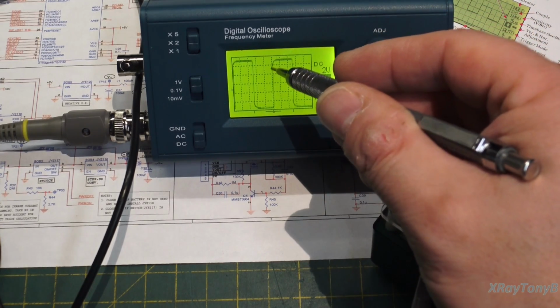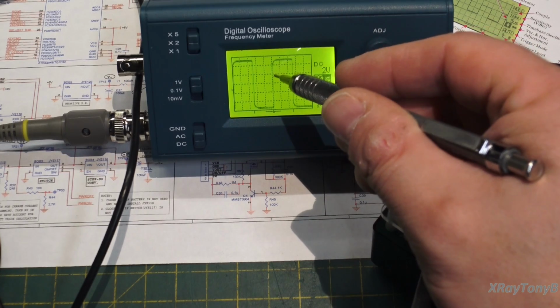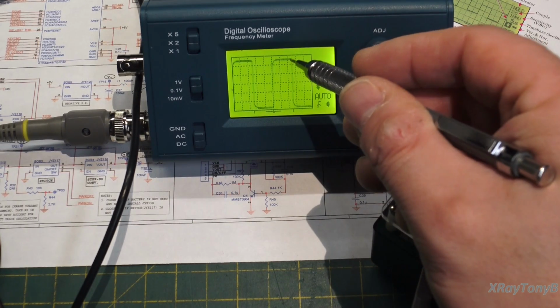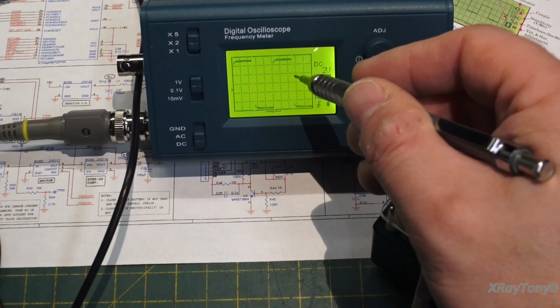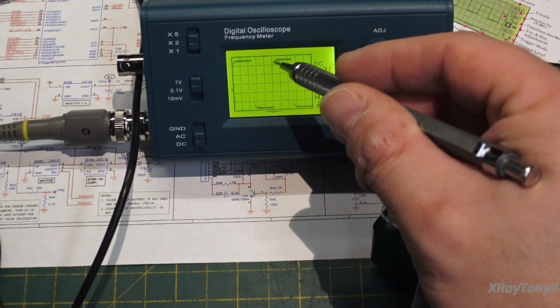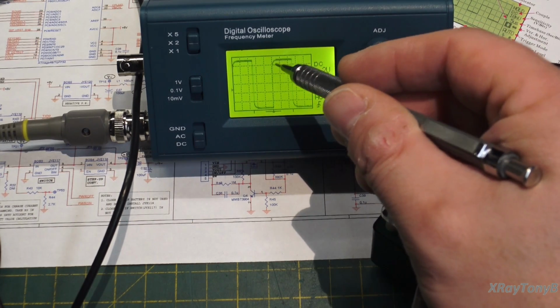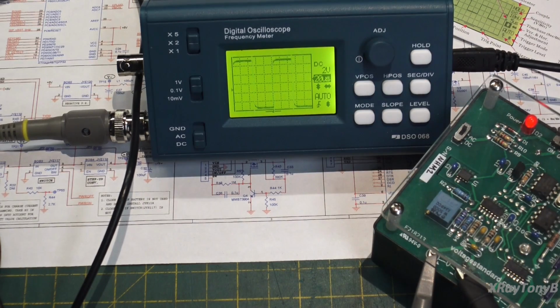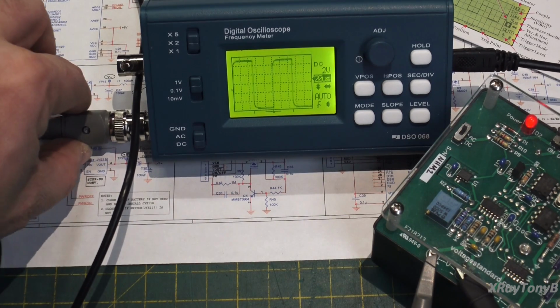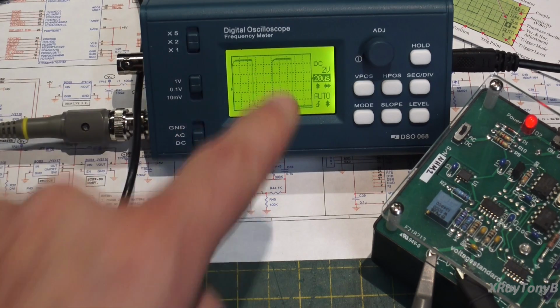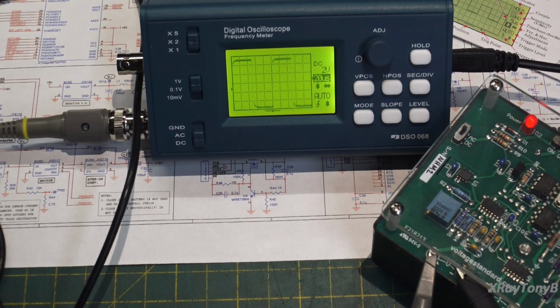You can see on our square wave we have a little curvature at the beginning. It's not square. On the downswing, it's nice and square, but on the rising slope, it's a little bit curved. And the reason for that is because the probe needs calibrated. And we looked at that on one of the other videos, and you can see right here is that little adjustment capacitor, and we're going to adjust that and see if we can get it to look square.